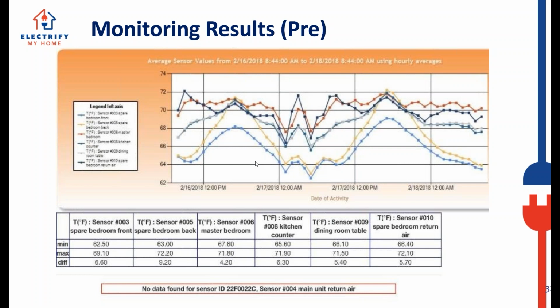This doesn't look comfortable. So through trials, tribulations, pulling out people from the manufacturer, changing some boards because there was a possible issue with that, adjusting things with the defrost wherever we could, resetting a number of dip switches and settings on the thermostats, we didn't get any real benefit out of this. And you'll be able to see on the next picture how long this took us to fix it. Fortunately, this was a customer in Napa and they didn't live in the house. So our whole thing with her is we would like to learn from this and fix it right, but can we do a little bit of research on it and figure out what's going on here, because we want to know what's happening so we don't do it again.